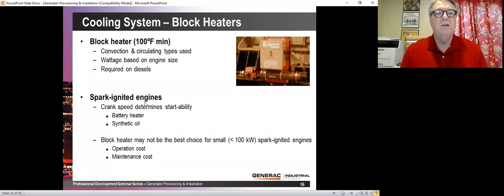Spark ignited engines, not as important in terms of heat, but very important that you get a good crank on that generator. So oil, the type of oil you use, and a battery heater will go a long way to make sure you get a good crank on that engine. Now, on larger generators or anywhere there's an emergency or legally required system, we typically put block heaters on them anyway. But on a lot of the small residentials, particularly in areas that don't get very cold, you don't really need a block heater.